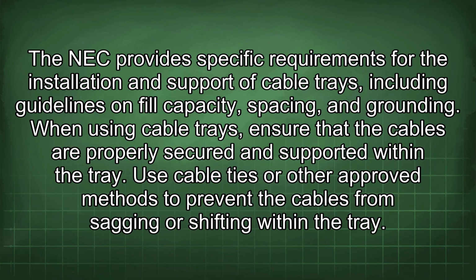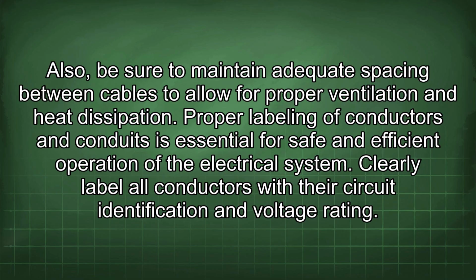When using cable trays, ensure that the cables are properly secured and supported within the tray. Use cable ties or other approved methods to prevent the cables from sagging or shifting within the tray. Also, be sure to maintain adequate spacing between cables to allow for proper ventilation and heat dissipation.